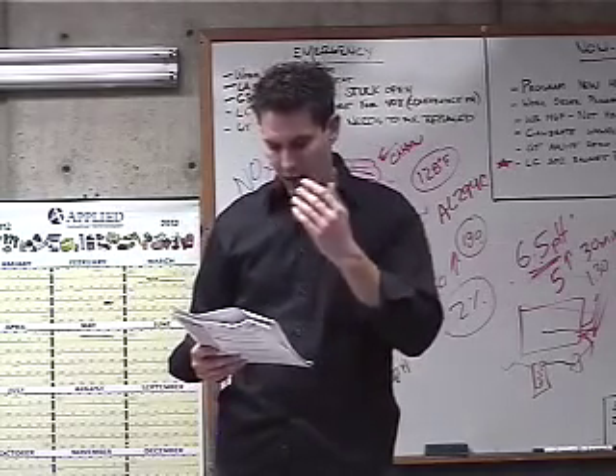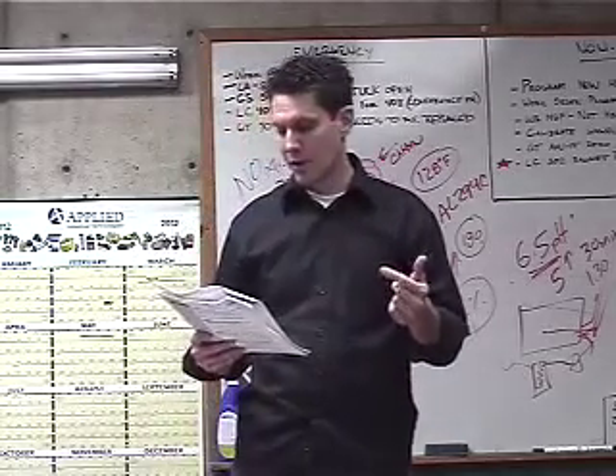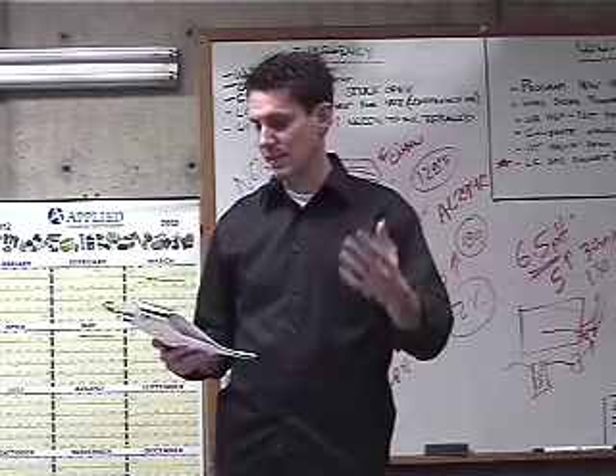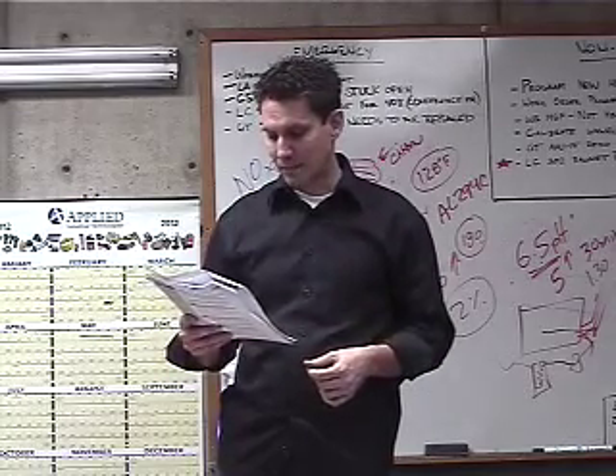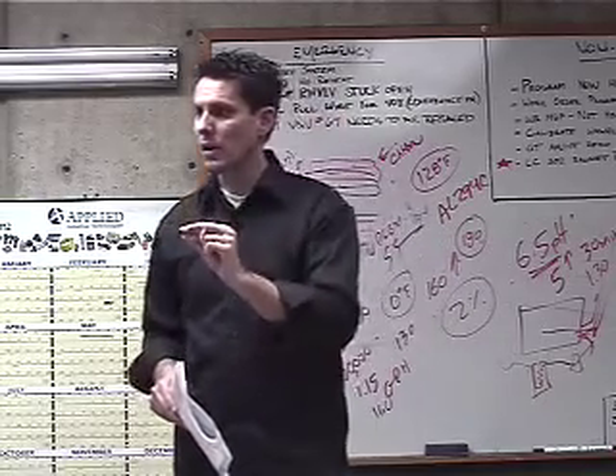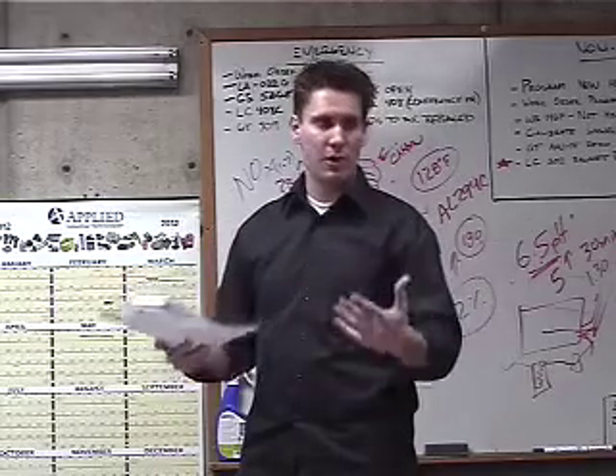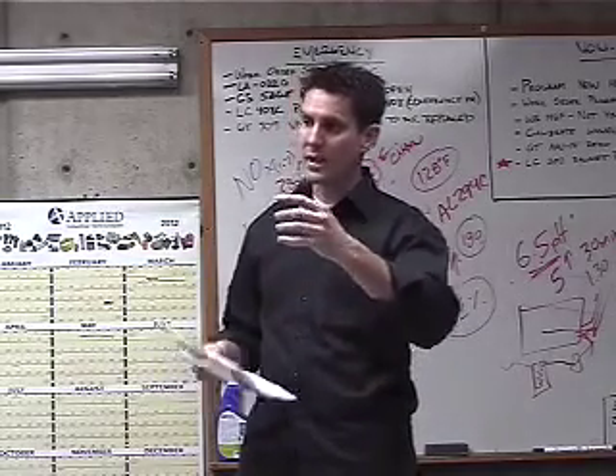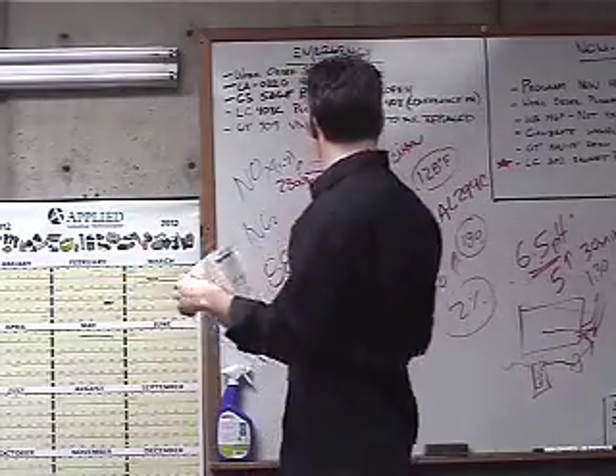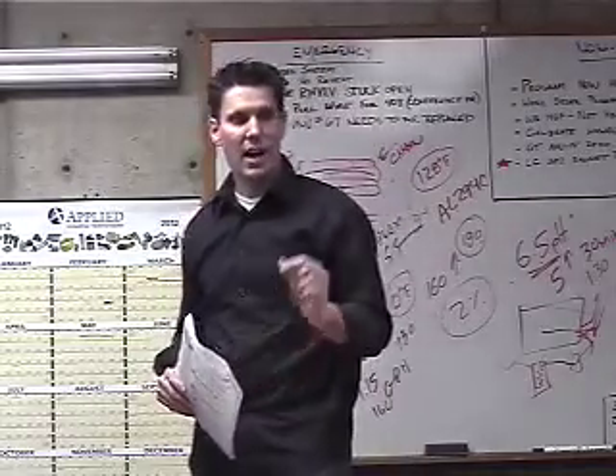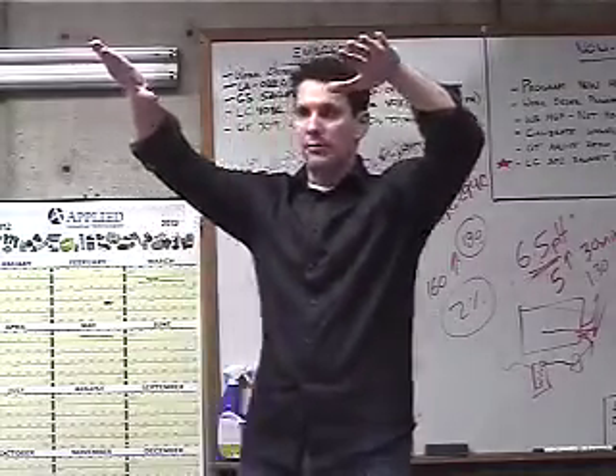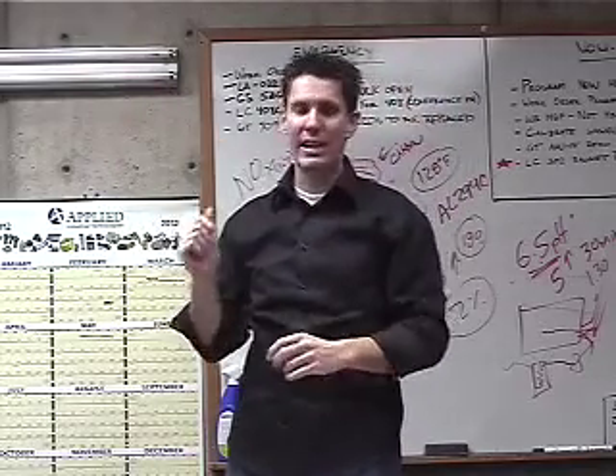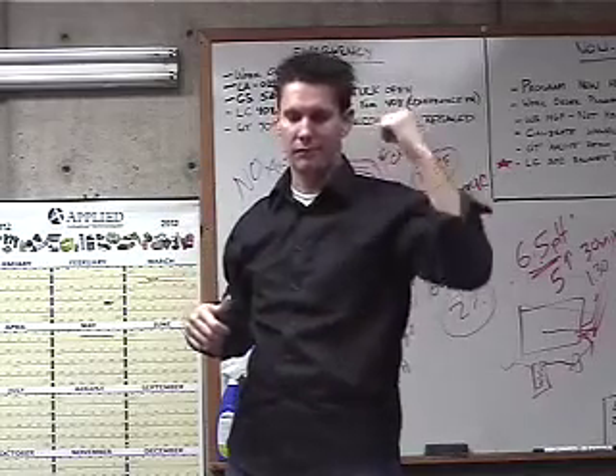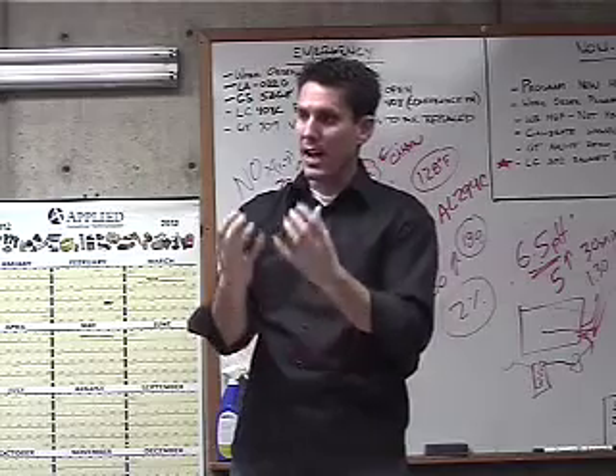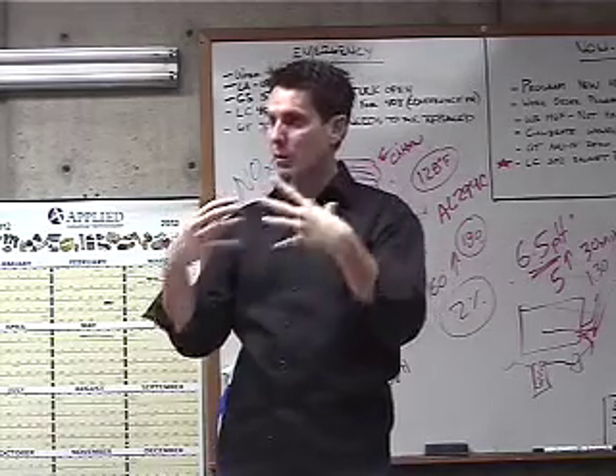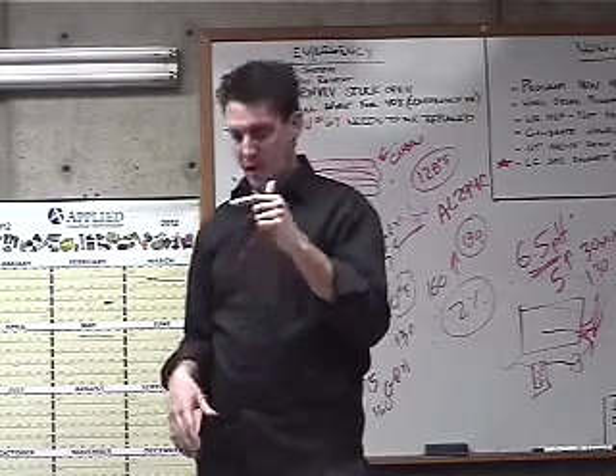The annual maintenance and inspection schedule. So annually, check the fuel train, the burner, and the control panel to make sure all the components are free of debris, free of dust, free of any sediment buildup. Examine the venting system. Again, there it is, the air intake and exhaust piping. Make sure, this is a pressure-powered boiler, a positive pressure boiler, so your stack is airtight. Not only is it watertight to prevent all that condensate from leaking out, but even though it's this AL294C, which is some of the highest grade stainless you can get, I have seen where condensate builds up. If you ever have your flue start to sag, your condensate will build up in there and it will eat through this. And I've seen that happen on many jobs where the condensate isn't drained out properly and it will eat through the metal. And as soon as you do, because it's positive pressure, you'll now blow products of combustion into the room. It's not good. So always, annually, check your flue.